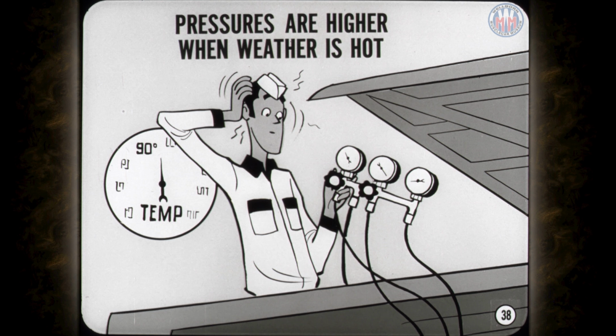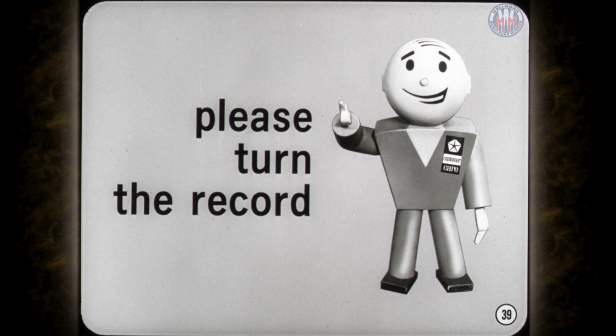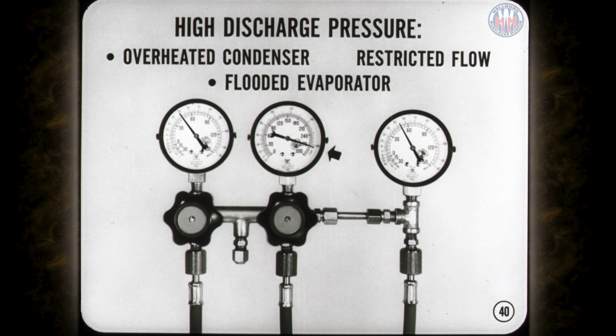Right now, someone had better turn the record over so Fred can tell us how to interpret the gauge readings. Good points, Tech. Now, if discharge pressure on the center gauge is higher than normal, between 240 and 300 pounds, it can mean an overheated condenser, restricted refrigerant flow, or a flooded evaporator.